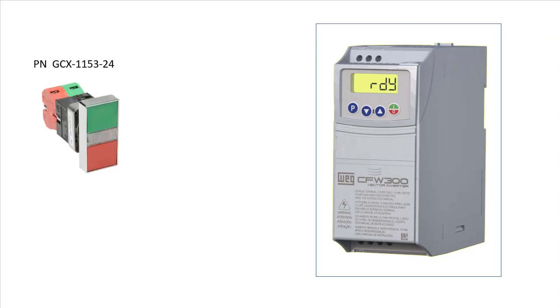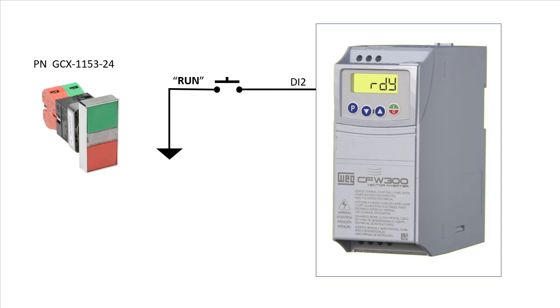I'm using this rectangular push button to provide one momentarily normally open contact to digital input 2, which will be our run command, and a momentary normally closed contact to digital input 3, which will be our stop command.